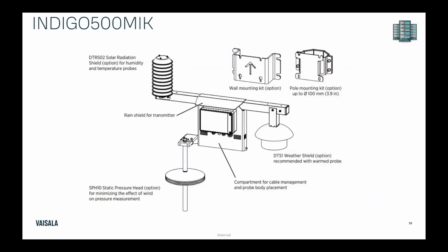And then here's that Indigo 500 MIK I mentioned before. You'll see the Indigo 520 right in the middle. That could be the Indigo 510, but the 520 makes a little more sense as it has dual probe support. On the left, this is typically a humidity and temperature probe, and on the right is for the warm probe enclosure. So the reason it's a different shape is because, as I mentioned earlier, if you have a heated probe, like the sunlight was heating up that environment, if a probe is artificially heated, it might heat up that radiation shield and cause a microclimate where it's going to mess up the readings because that temperature is being artificially warmed and changing any of the temperature dependent parameters.